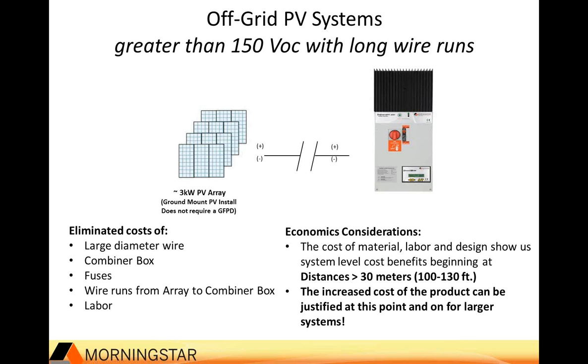One of the biggest benefits of this product used in just standard solar applications is the fact that you're wiring the input voltage usually at an operating point of 300 to 400 volts. What that does is give you a lot greater distance that you can run the PV array before you have to convert down to low voltage to charge the battery. For that reason, we have a lot of new advantages, especially economic considerations, that allow you to do systems that you weren't previously able to do.